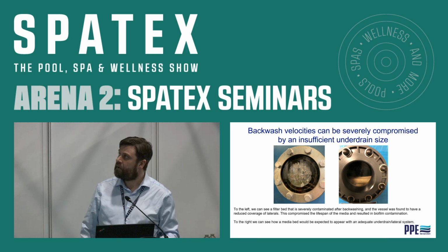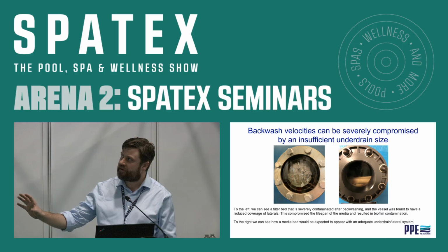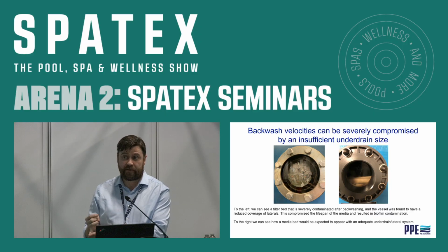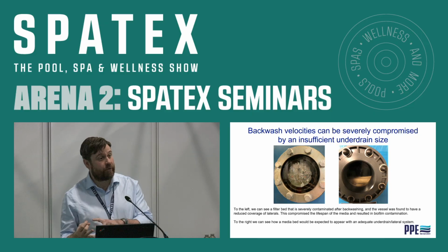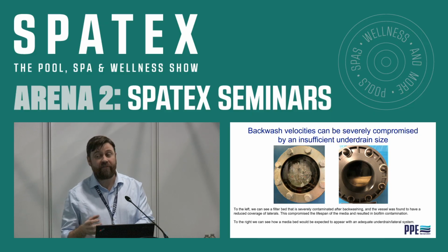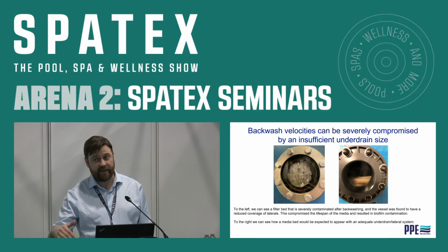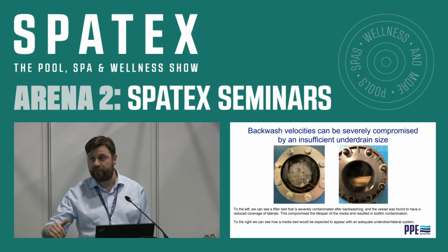And probably your first telltale signs, before it gets this bad, you'll be seeing failures on your microbiological testing, increase in chemical costs and chemical consumption. But if you use more chlorine, you're going to use more acid. What's going to happen to your water balance index? TDS is going to go higher. The more acid you use, the more alkalinity you take out.